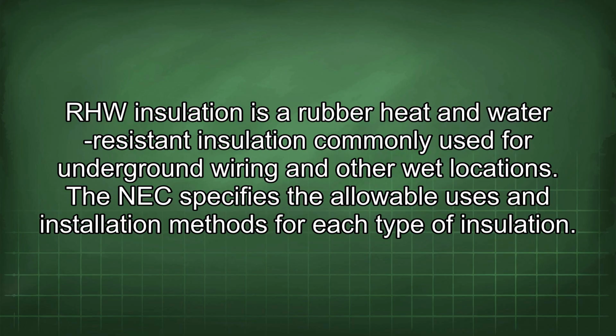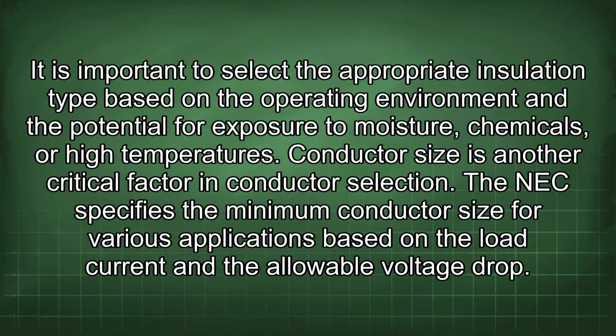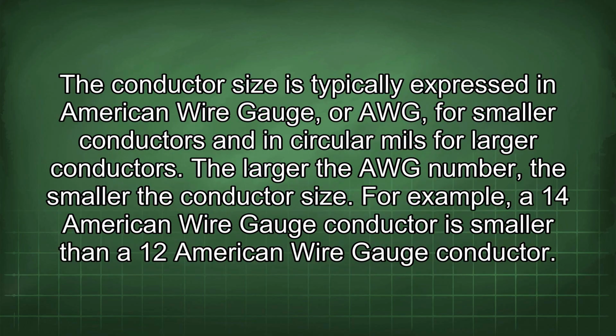RHW insulation is a rubber heat and water resistant insulation commonly used for underground wiring and other wet locations. The NEC specifies the allowable uses and installation methods for each type of insulation. It is important to select the appropriate insulation type based on the operating environment and the potential for exposure to moisture, chemicals, or high temperatures. Conductor size is another critical factor in conductor selection. The NEC specifies the minimum conductor size for various applications based on the load current and the allowable voltage drop. The conductor size is typically expressed in American wire gauge, or AWG, for smaller conductors and in circular mils for larger conductors. The larger the AWG number, the smaller the conductor size. For example, a 14 American wire gauge conductor is smaller than a 12 American wire gauge conductor.